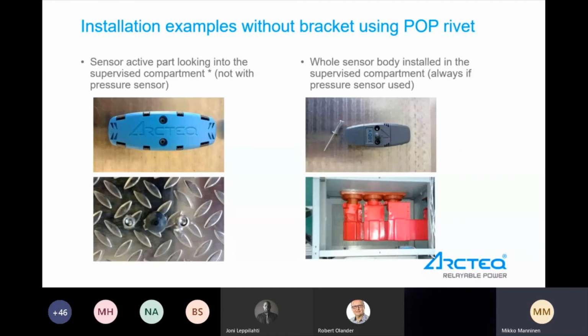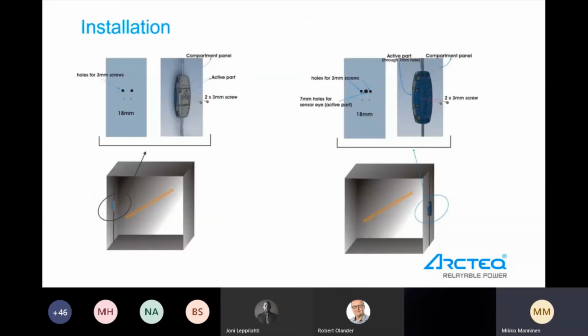Point sensors can be mounted both ways. They can be mounted outside of the box or inside the box. I personally like the inside compartment installation more. And of course, the pressure sensor always has to be inside the compartment, not outside. The compartment for the pressure sensor also has to be quite tight. There should not be any air louvers or such openings. And the point sensor can easily see 1.5 meters inside the compartment.